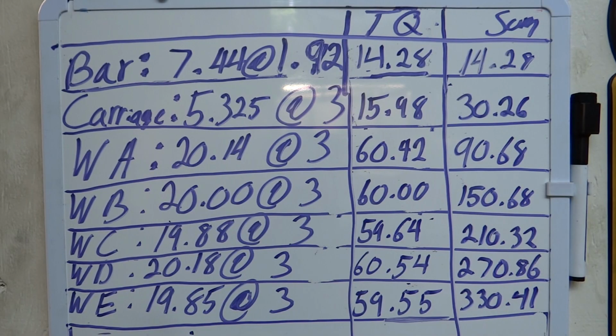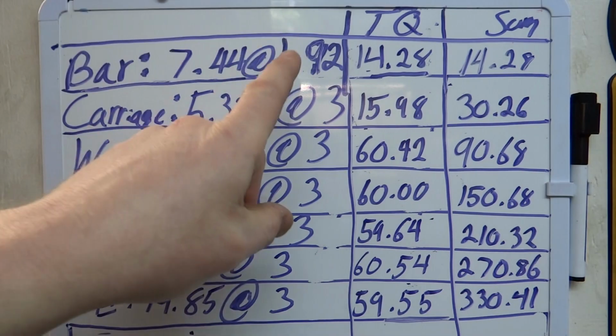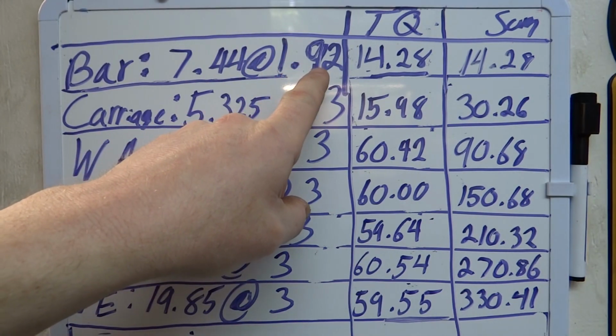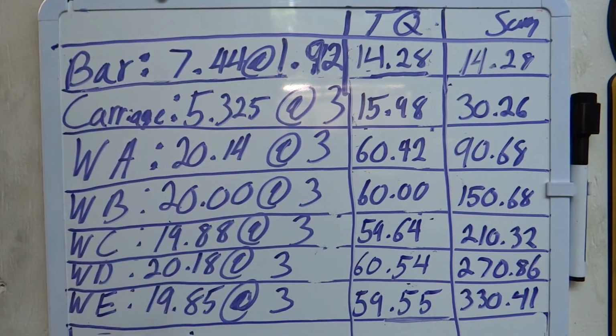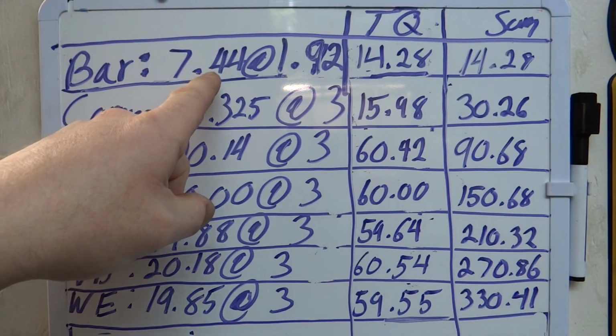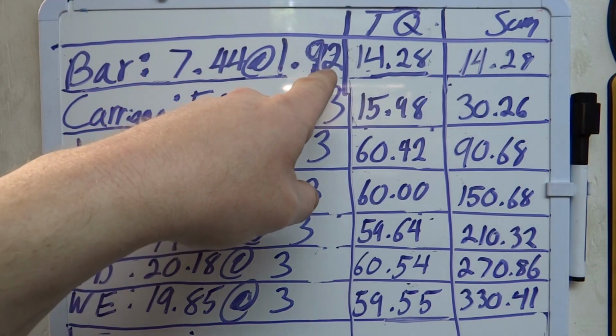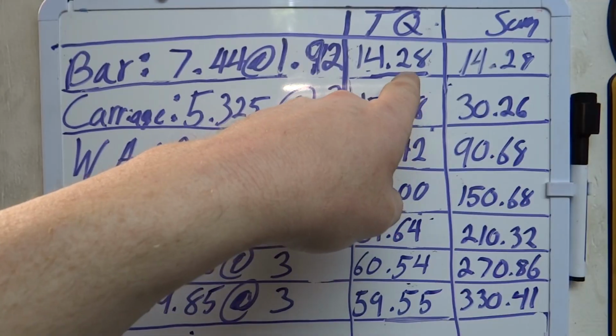I'm going to have 7 things attached to the dyno to get the calibration done. The first is the bar I just showed you, which weighed 7.44 pounds with its center of gravity 1.92 feet from the center of the absorber. So we multiply 7.44 by 1.92 and get 14.28 foot-pounds.